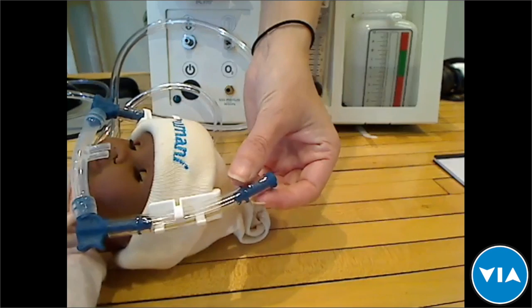So I think that was the question about leaks. There are also alarms inside of the machine. If there are leaks in the system, the total flow will not be as high as it should be. So that will alert the user that there may be a leak in the system, and the user can go into the machine and reattach the tubing if they see that there's a leak. Or it's possible they may hear it as well. But leaks inside of the system should not be happening.